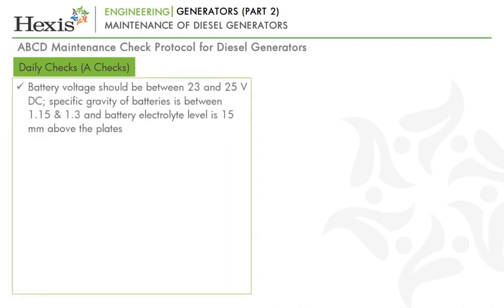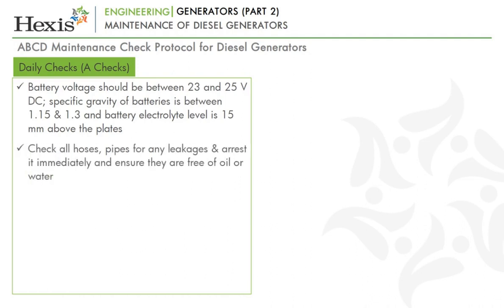Check the battery voltage. It must be between 23 and 25 VDC. The specific gravity of batteries must be between 1.15 and 1.3. The battery electrolyte level should be approximately 15 mm above the plates. Check all hoses, pipes for any leakages and arrest it immediately. Ensure that the pipes and hoses are free from oil and water traces. Check the intake air restriction indicator if available.